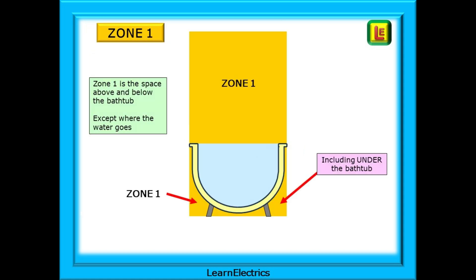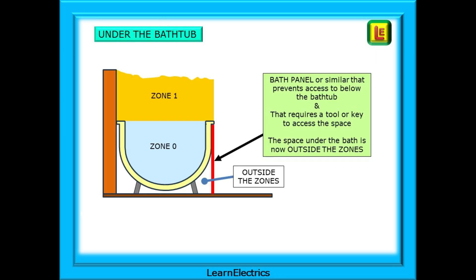Zone 1 is the space above and below the bathtub that is not zone 0. Remember, this includes the area under the bathtub unless something else happens. In this drawing the bathtub is against a wall on one side and a bath panel has also been installed. If the bath panel requires a tool — a screwdriver or a key to remove it — then the space under the bath is classed as being outside the zones and not zone 1.